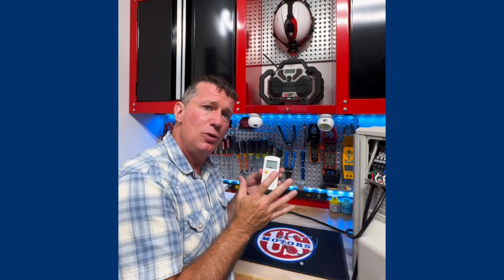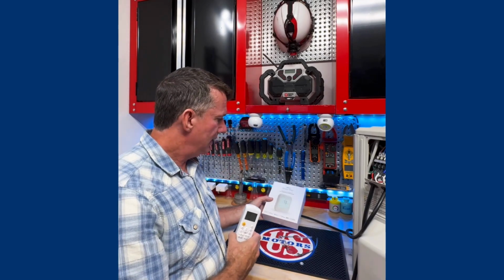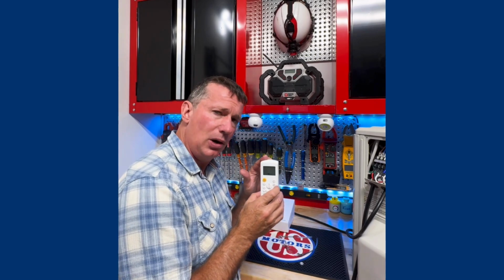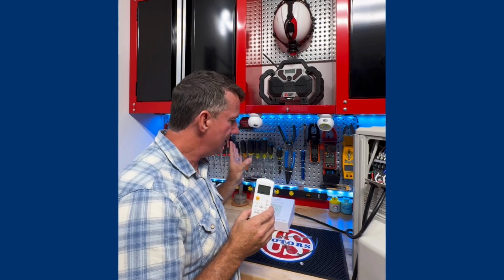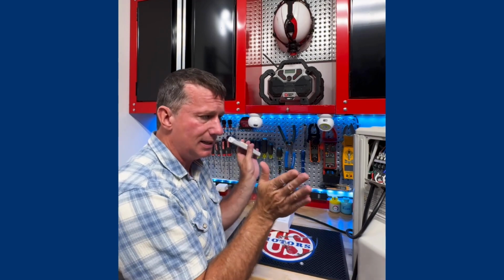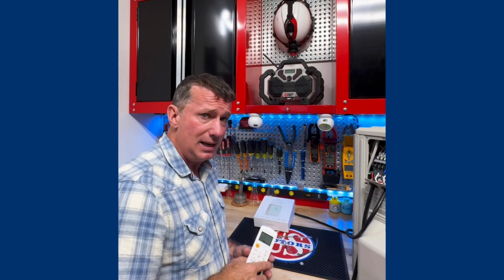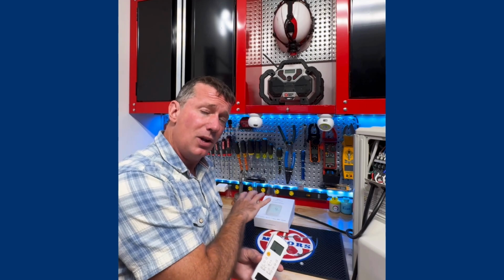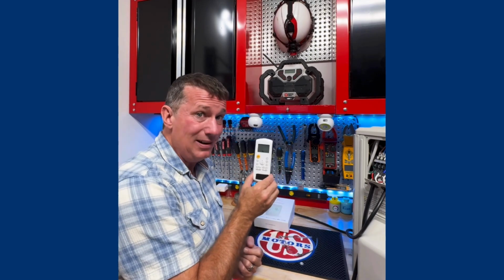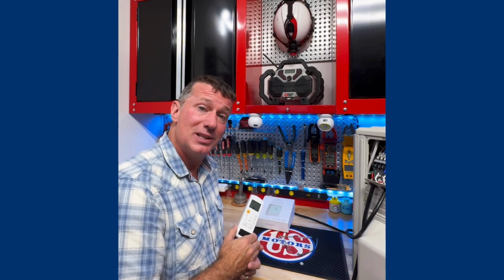like. And now we have new products coming to the market like this CIELO Breeze Max, which I really enjoy, that is a more traditional looking thermostat, and you actually pair the IR remote with that thermostat, and then it's able to send those IR signals from the thermostat back to that indoor unit. It needs to be within line of sight by a certain amount of degrees just so that it can read those light signals. But it truly is a thermostat that can be mounted on the wall or mounted on the tabletop as long as it has power supply, and now can act like a wireless thermostat. It's actually just a repeater wireless thermostat.